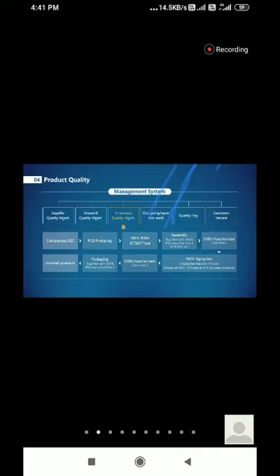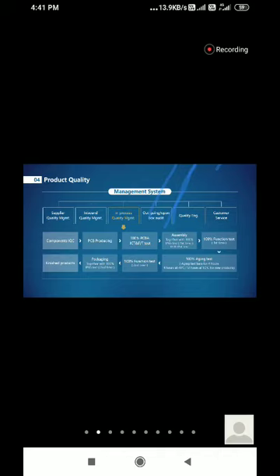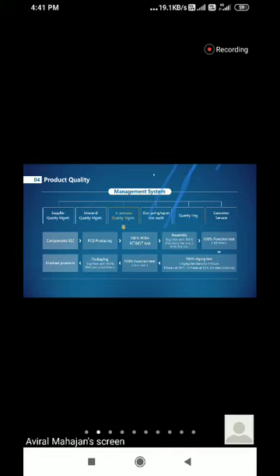After functional testing, the product moves to the assembly section where all PCBs and different cards are assembled into the inverter housing. After that, IP65 testing and high potential testing are performed. When a single product passes all these parameters, it proceeds to a 100% aging test performed twice — first at 40°C for four hours, then at 60°C for six hours. After all product testing, it goes to packing and finishing.